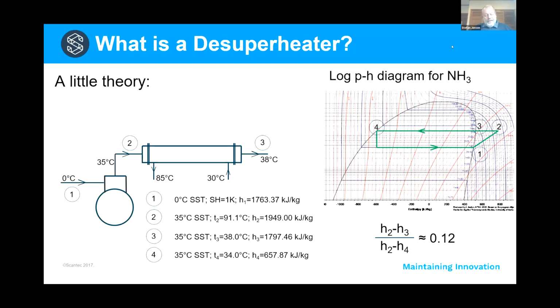Now, it's important to note here that in an ammonia plant, we can only recover roughly 12% of the entire condenser heat rejection. This is assuming we have reciprocating compressors. If we have other types of compressors like screw compressors, that 12% is less. More about that later. But here's what I've tried to show with that little formula down the bottom. In this particular case, we can recover high-grade heat to the tune of 12% of the total condenser heat rejection that comes out of that compressor, or it can be multiple compressors that operate in parallel.